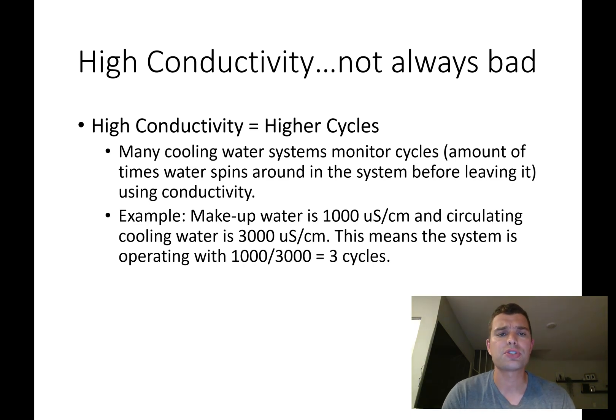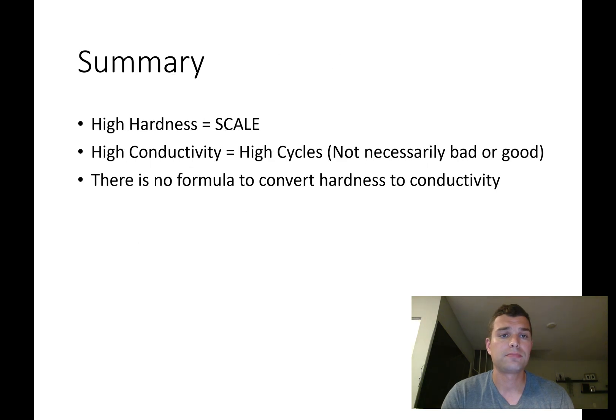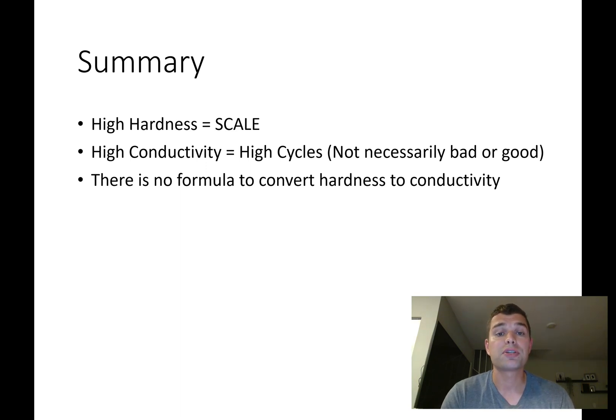If you have all the other chemicals in check and you're designed to operate at higher cycles, then higher conductivity is not necessarily bad. In summary: high hardness means scale — calcium carbonate — which is not good. High conductivity means you're probably at higher cycles, which may or may not be good depending on your design. And there is no formula to convert directly between hardness and conductivity, so you can't use one to calculate the other.